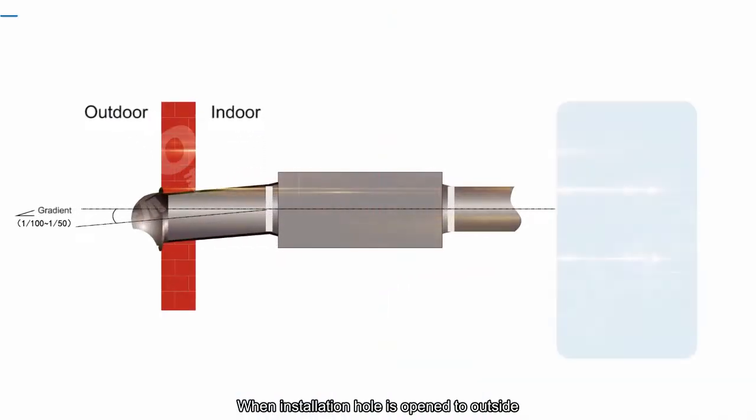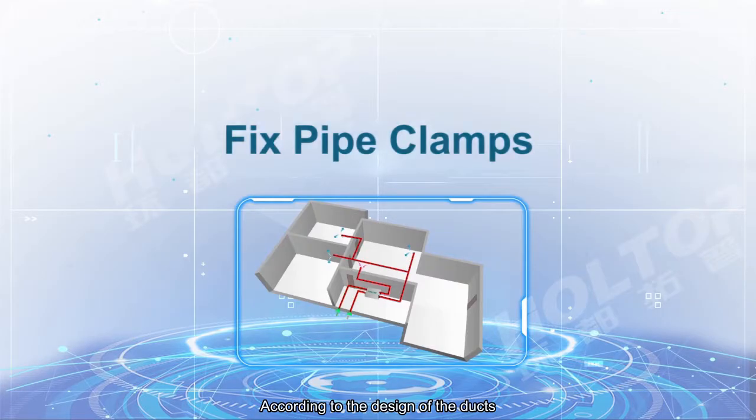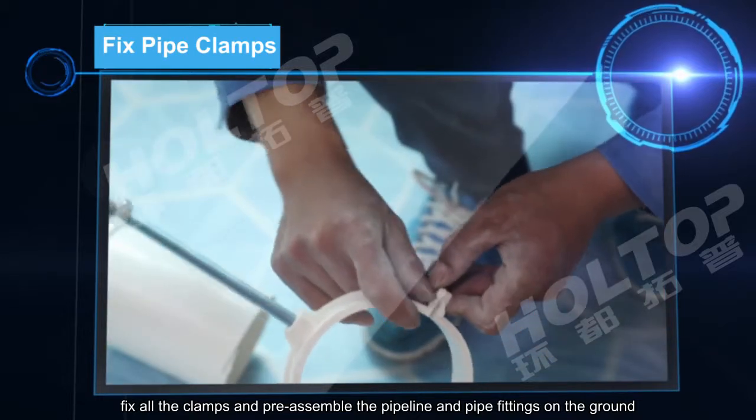When the installation hole is opened to the outside, it should be tilted with an inclination of 1% to 2% to prevent rainwater from entering. According to the design of the ducts, fix all the clamps and preassemble the pipeline and pipe fittings on the ground.